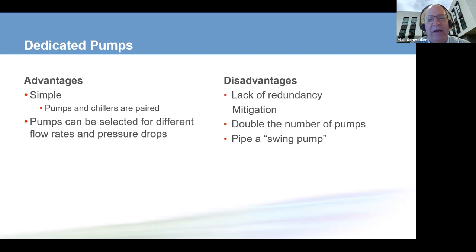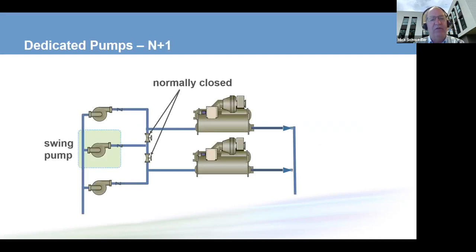but there's some drawbacks. When we dedicate pumps, we don't have the same redundancy. We can mitigate that. We could either double the number of pumps or pipe in what's sometimes referred to as a swing pump. So in this case, we have a pump dedicated for each chiller.